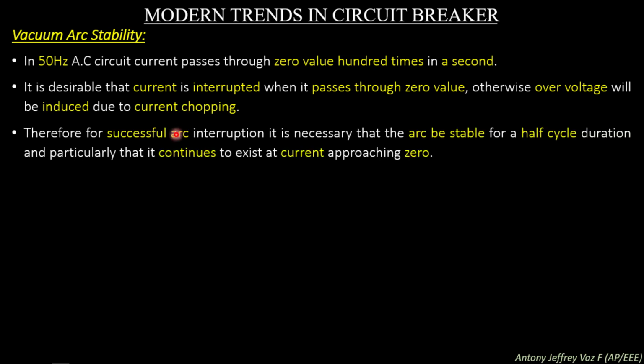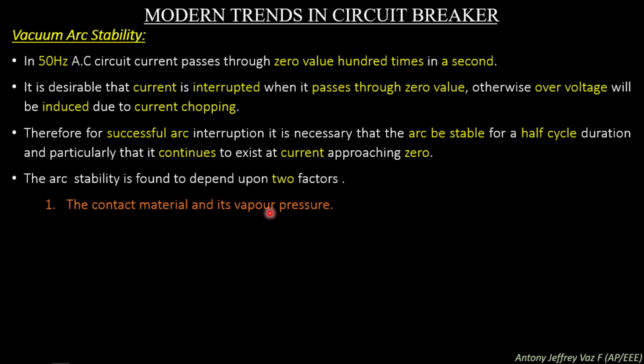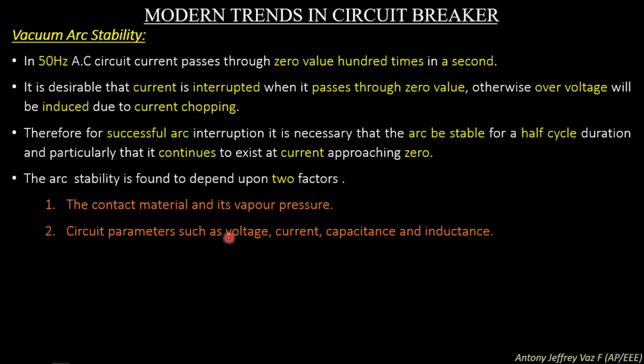Therefore, for successful arc interruption, it is necessary that the arc be stable for half cycle duration, and particularly that it continues to exist at current approaching zero. The arc stability is found to depend upon two factors: the contact material and its vapor pressure, and circuit parameters such as voltage, current, capacitance and inductance. So these two factors determine the stability of the arc formation.